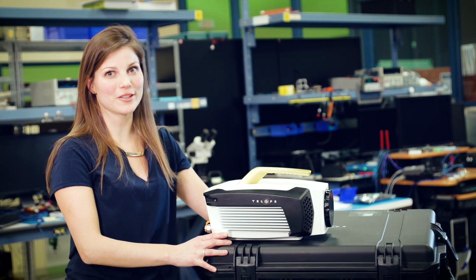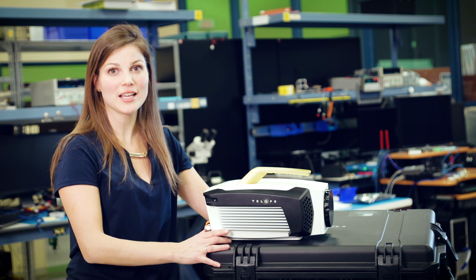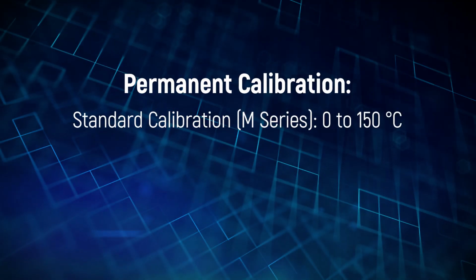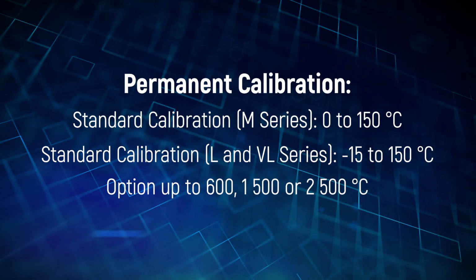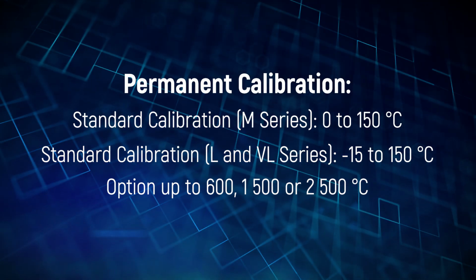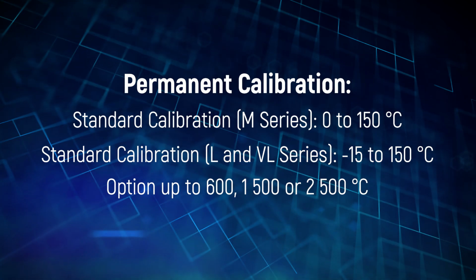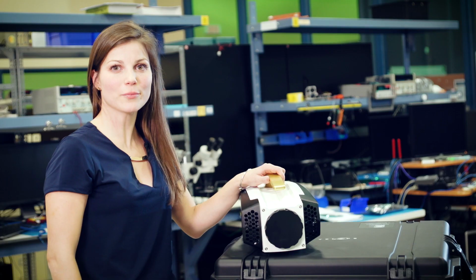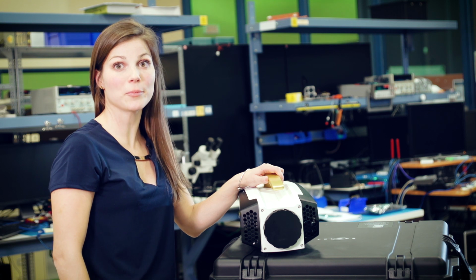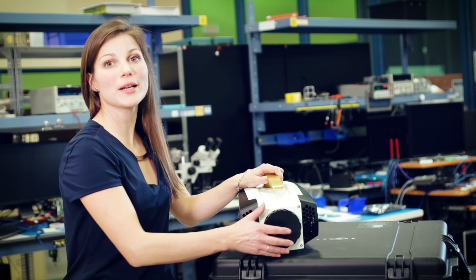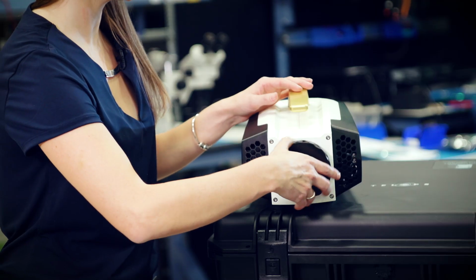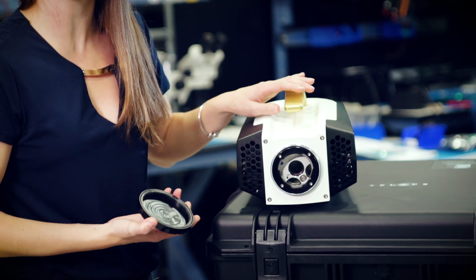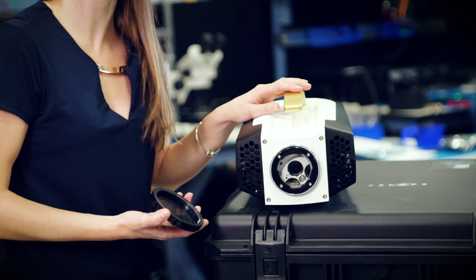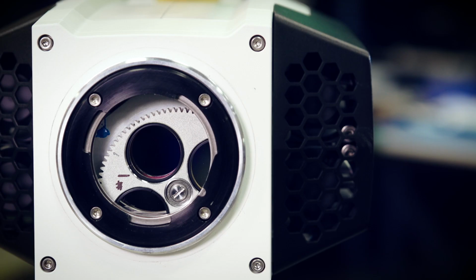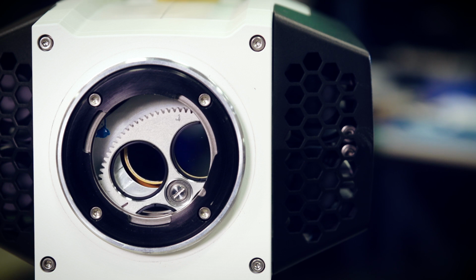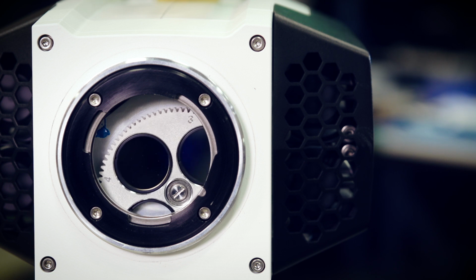The standard calibration for mid-wave camera, like the Fast M3K, is allowing temperature measurement between 0 up to 150 degrees Celsius. And for long-wave cameras, it allows temperature measurement between -15 and 150 Celsius degrees. Temperature calibration range can be extended up to 600, 1500, and 2500 Celsius degrees by adding some neutral density filter in the motorized filter wheel that is present in all our cameras from the Fast IR series. Any 1-inch diameter filter or combination of filters can be inserted as long as their thickness does not exceed 2 mm.